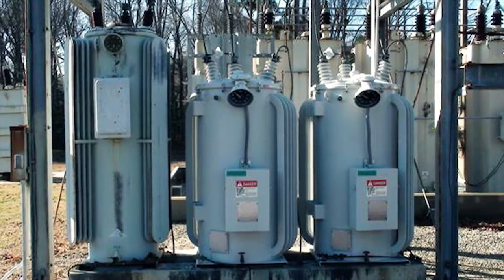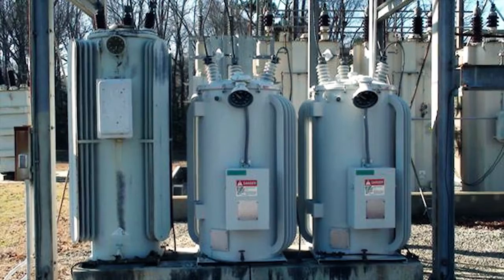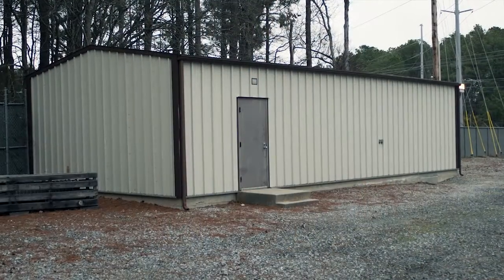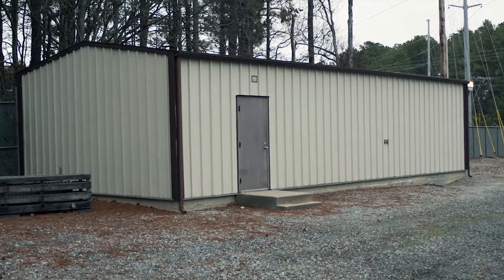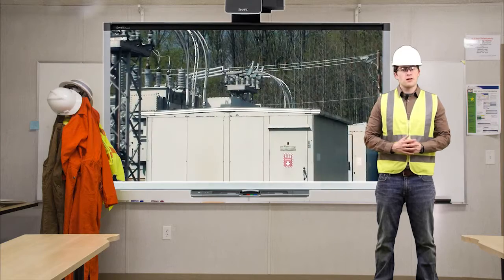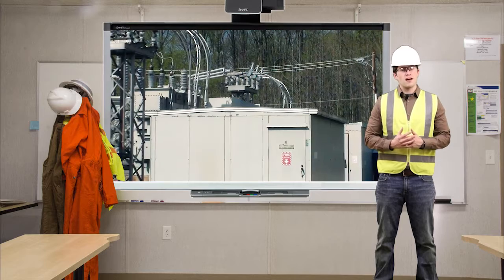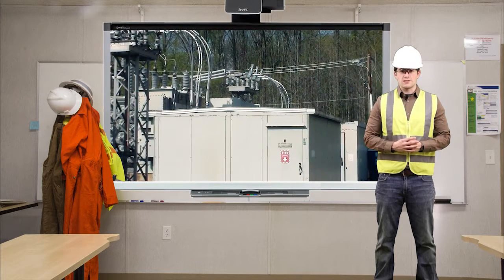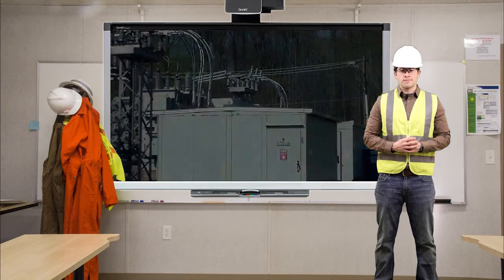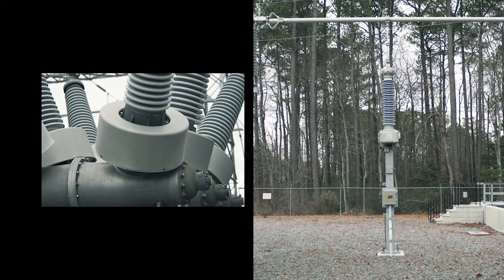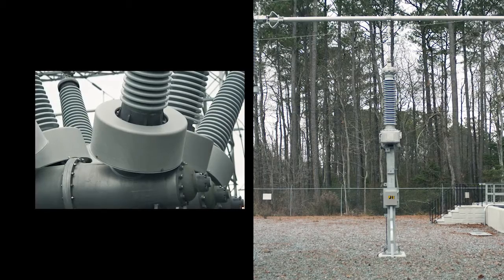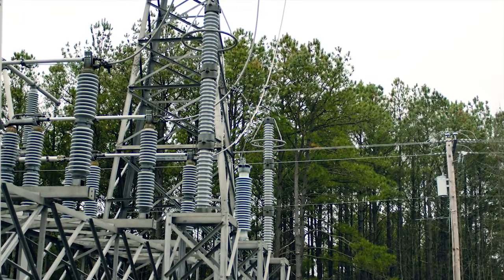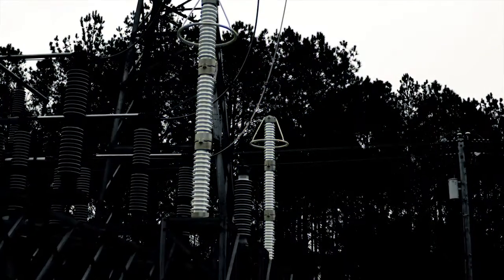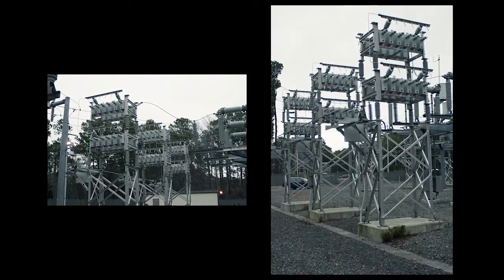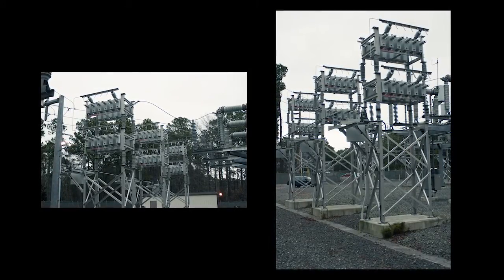Voltage regulators are used to maintain voltage on distribution systems for changing system loads. Control houses are used to protect control equipment from the elements. Some substations have metal-clad switchgear which provide housing for circuit breakers, protective relays, and other control equipment. Current transformers and potential transformers monitor current and voltage for metering and relaying. Lightning arresters protect the substation equipment from lightning strikes and switching surges. Capacitor banks are used to eliminate the voltage drop in the system caused by inductive loads such as motors.